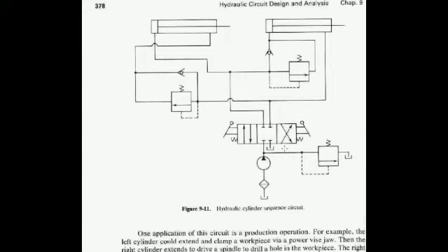So in the right envelope, the pump port will be connected to the B port. That means this line, right? So the fluid flow will take place to the rod end of the second cylinder, as well as that will flow in this manner and this manner. Here it is going to be blocked. Here we will not be getting that much of a pressure in this line to open this sequence valve, right? So that I will get the retraction motion of this one.